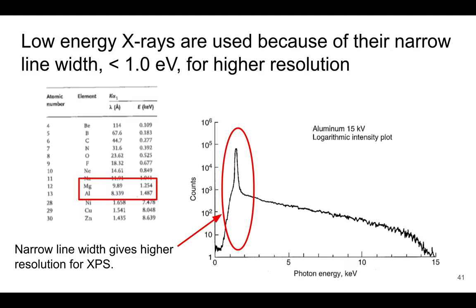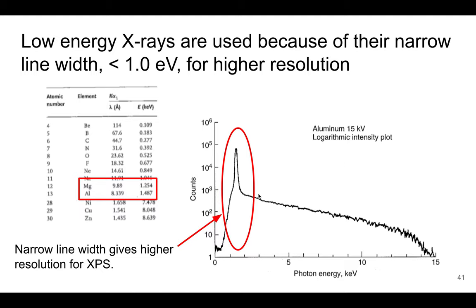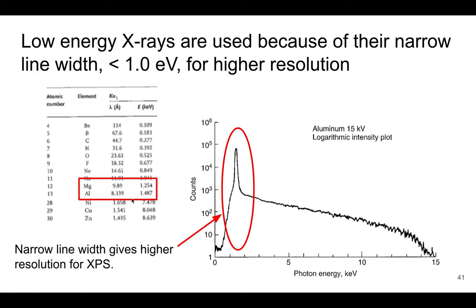The reason we use aluminum or magnesium is that they have lower energy, which produces a very narrow K-alpha peak. That narrow line width gives us higher resolution. Looking at the curve shown here — aluminum at 15 kV — the K-alpha peak is very narrow in energy. Magnesium and aluminum both have much lower energies compared to copper, and that lower energy means a narrower line width and therefore better resolution.